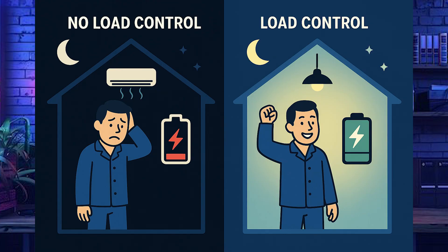The gateway has some other benefits too. Besides powering your lights, the gateway enables integration with a generator, so you can recharge your battery when solar isn't enough. The gateway also allows a connection to your EV charger, so you can future-proof your solar for when you get an EV. It also allows smart circuit and load management — it can shed heavy loads like your AC or electric range automatically during outages so that your battery lasts longer.